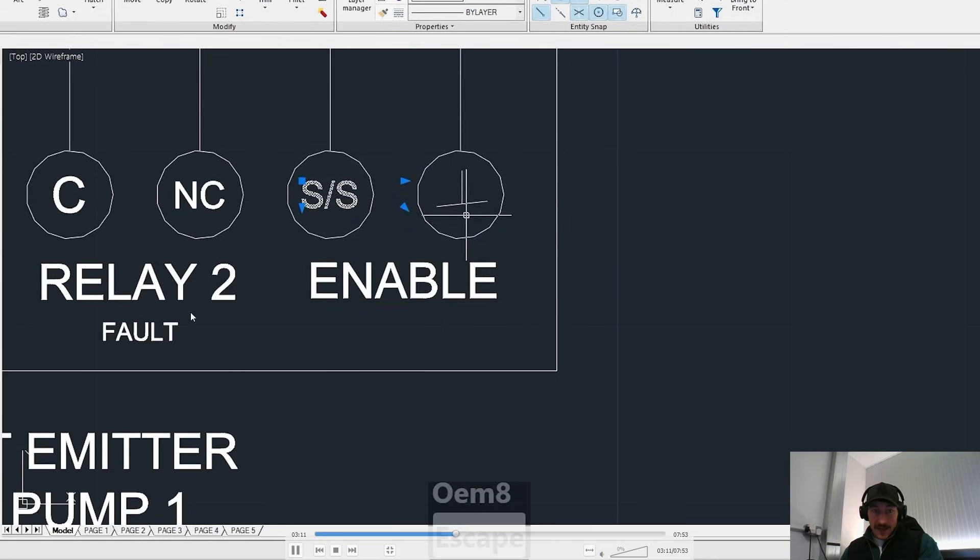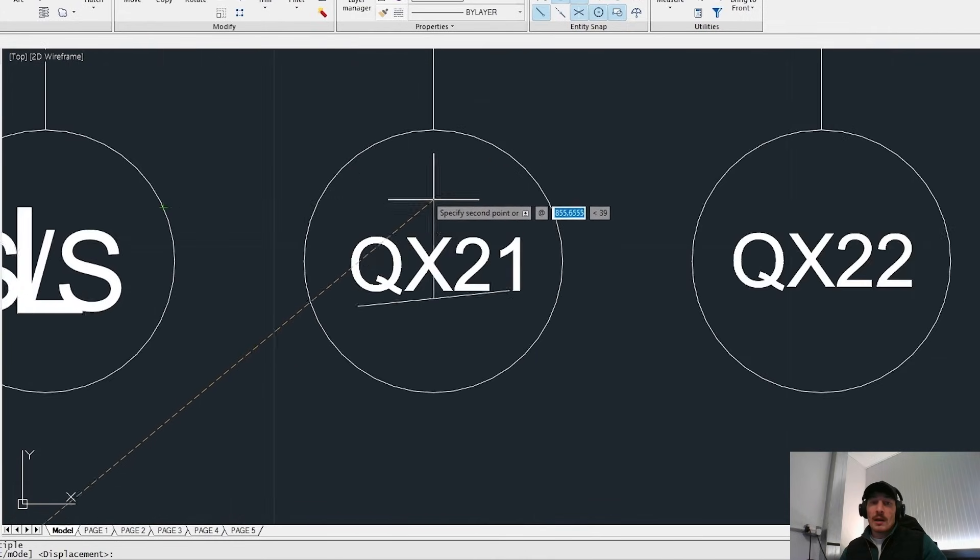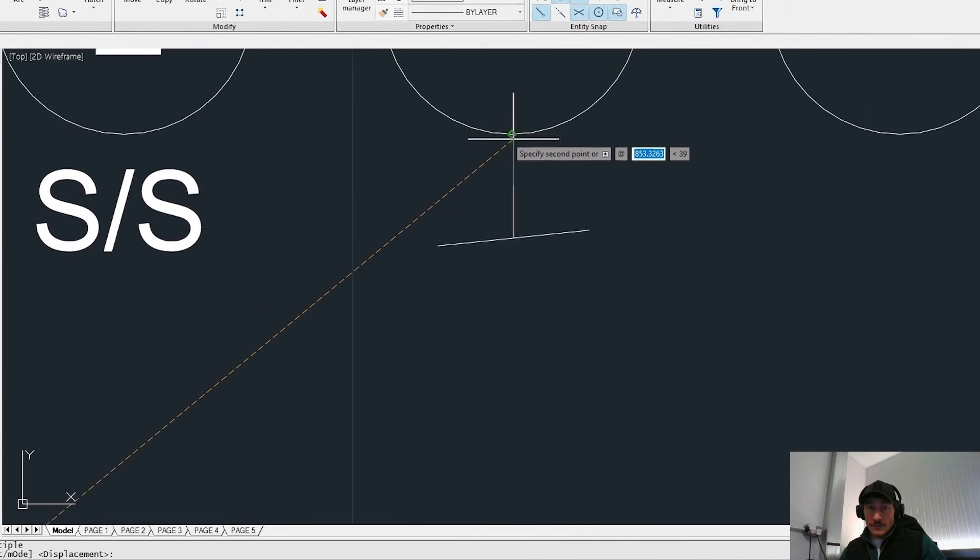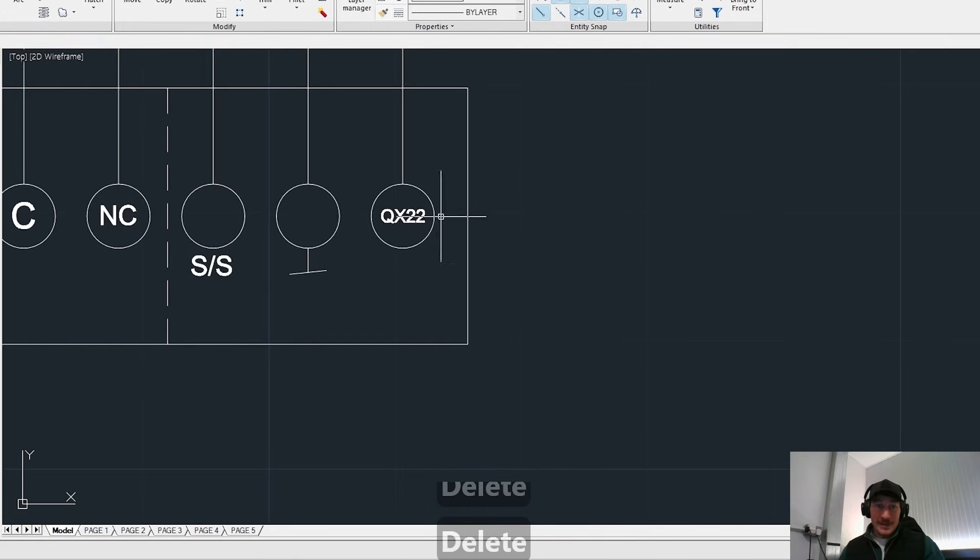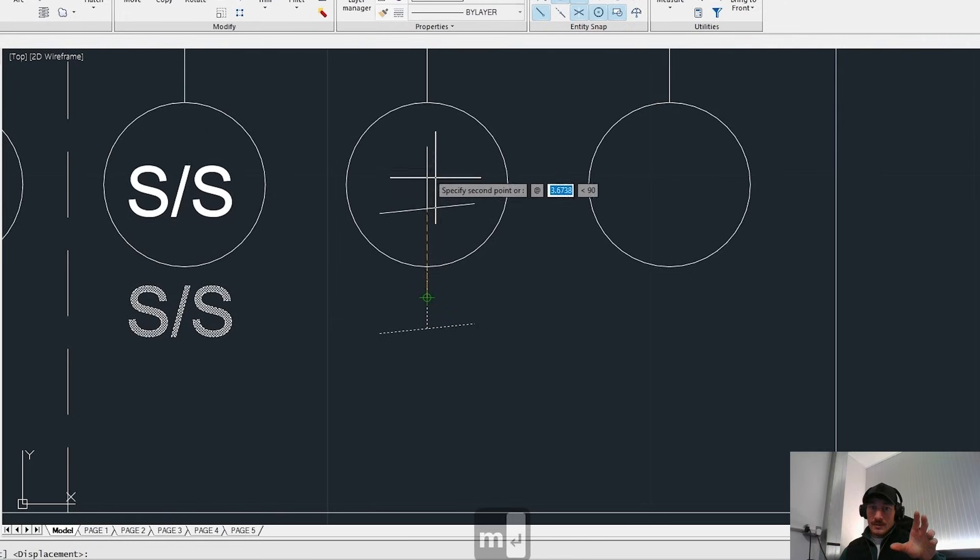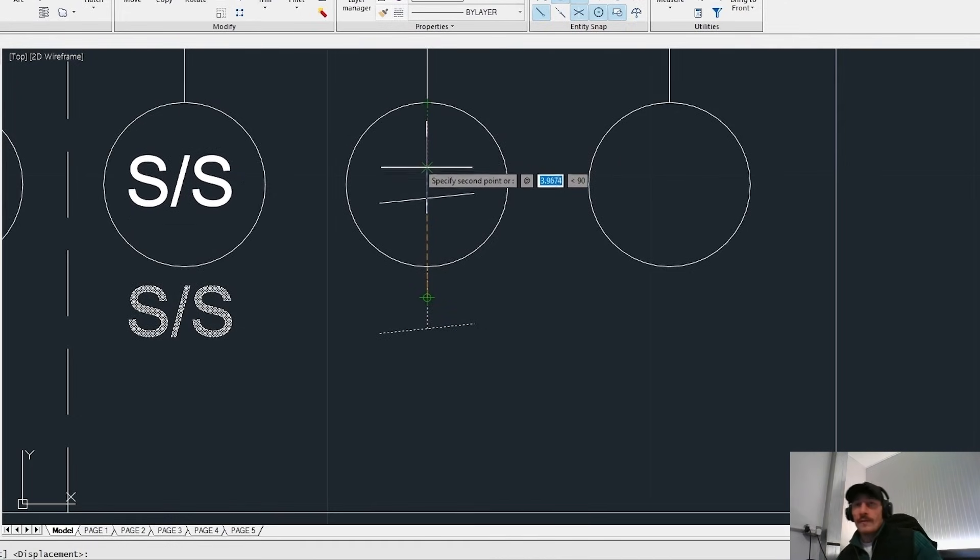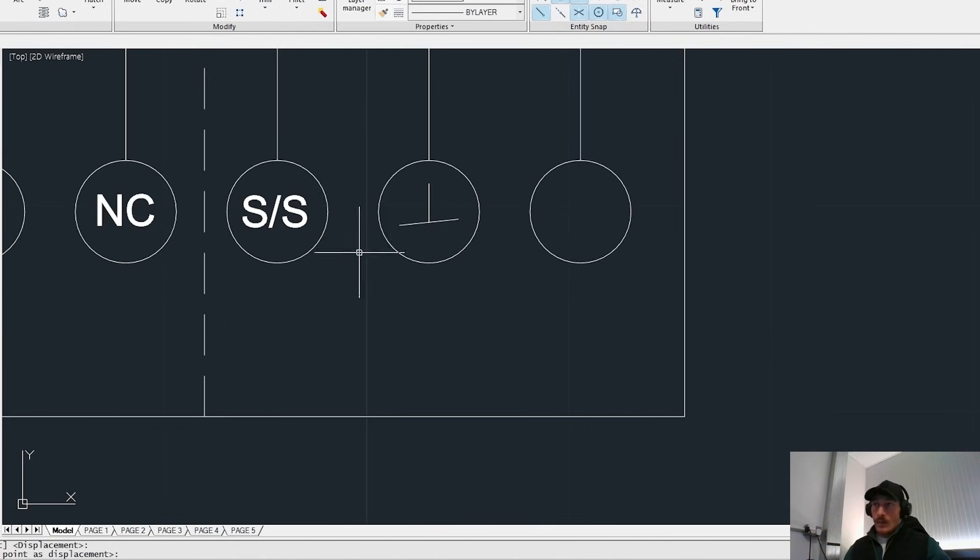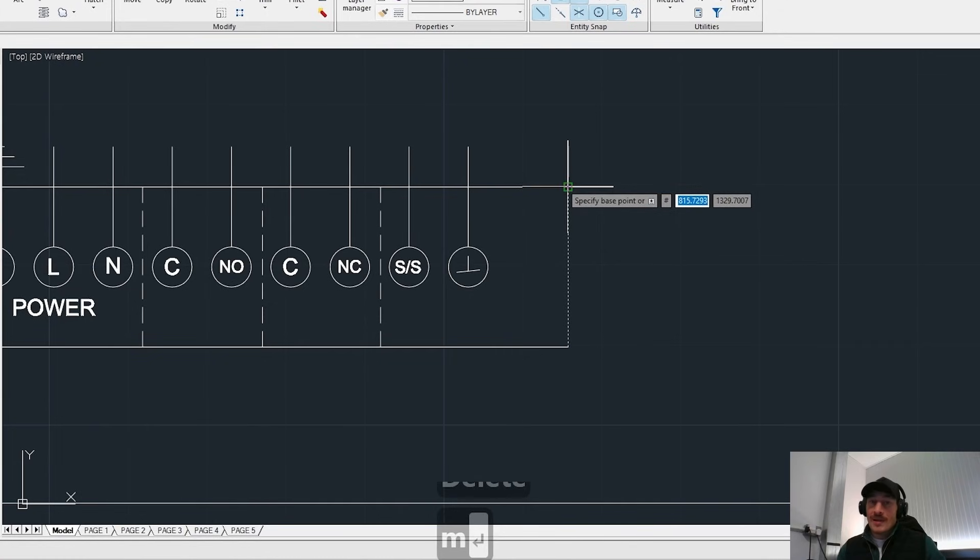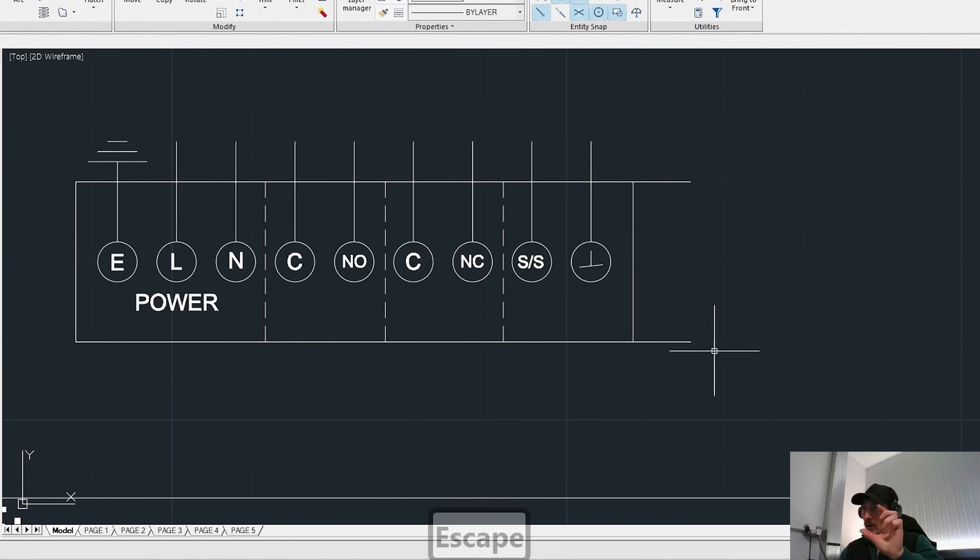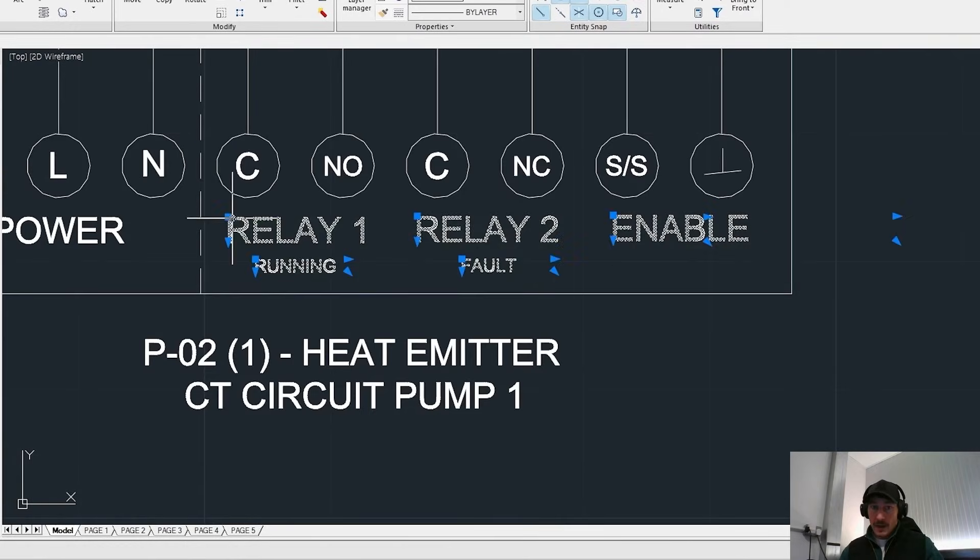As you can see, we got a common and normally closed and it's difficult as a designer. Generally speaking, you always wire in the normally closed. It depends on the application actually. But what I've done is I've worked out that this should be wired normally closed. So I don't need to add in the normally open connections. Now, if the guys on site realize that that needs inverting, then they would just red pen out that NC, normally closed and change it to NO, normally open. So it's difficult for designers sometimes to get that around the right way. And that's where a lot of the time commissioning engineers might need to red pen it and switch it from normally open to normally closed or normally closed to normally open based on what's going on on site.